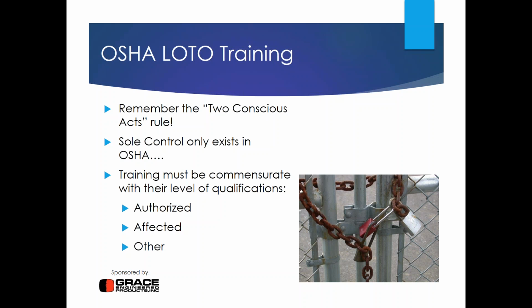Meaning that every authorized person must first be qualified as defined in the training requirements for the piece of equipment that they're going to lockout tagout. Then they must take a company-specific lockout tagout training program, which includes about a 4 or 5 hour classroom instruction, a written test for cognitive learning, and then they must go out in the field and demonstrate proficiency on the type of equipment on which they were going to be locking out. And they need to demonstrate that in front of somebody who themselves is an authorized employee who has been trained as a trainer, if you will, to assess their skill. At the end of all that, they are issued their locks and tags.